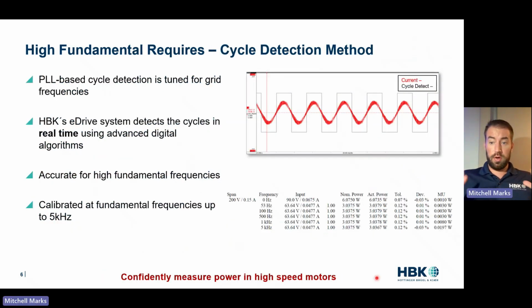One method we see to overcome this issue of the high fundamental frequency, and I made this slide out of order, but let's start down here. This is an example from a calibration sheet where we're calibrating for 0, 50, 100, 500, 1 kilohertz, 5 kilohertz. You can see the tolerances steadily increase because it's getting more and more difficult to measure power at those higher fundamentals. One thing many of you might not know is that traditional power measurements are usually made with a phase lock loop-based system, which is quite slow and also tuned for grid frequencies, 50, 60 hertz. If you have this phase lock loop that's looking for 50, 60 hertz, it's really going to struggle at 100, 500, 1,000 hertz.